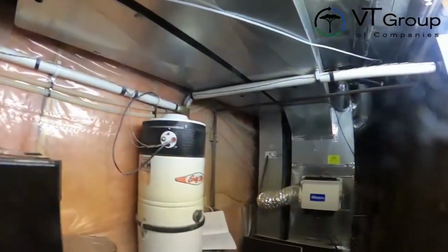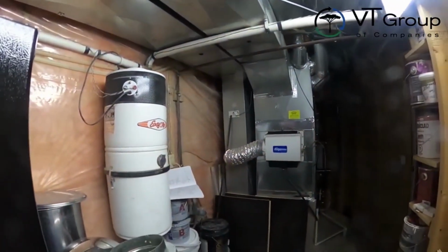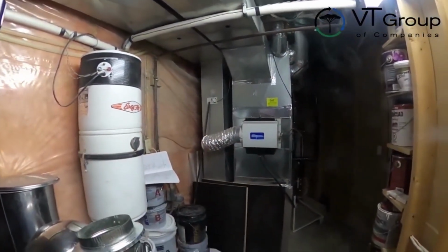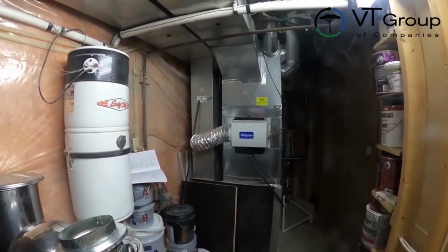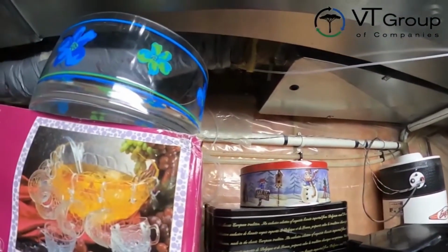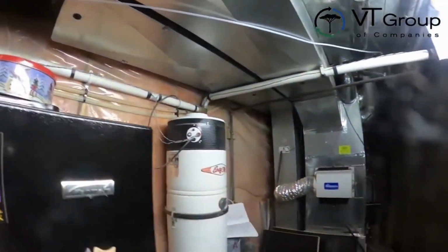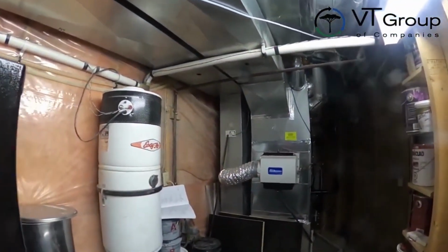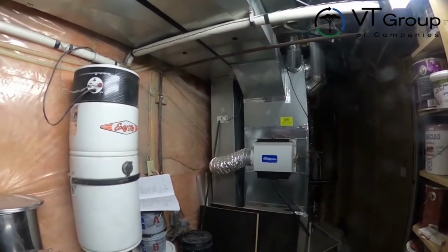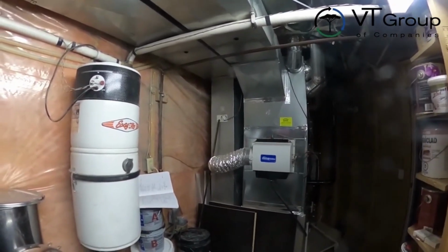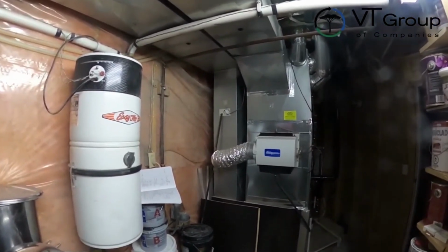As you can see, if I look at the furnace, on the left-hand side is my return air. So when the furnace fan is running, what is happening is there's a negative pressure in that ductwork. Outside air will be drawn in. Outside air will be drying out the house. If that is interlocked with your bathroom exhaust fan, what that means is air is being exhausted to the outside.